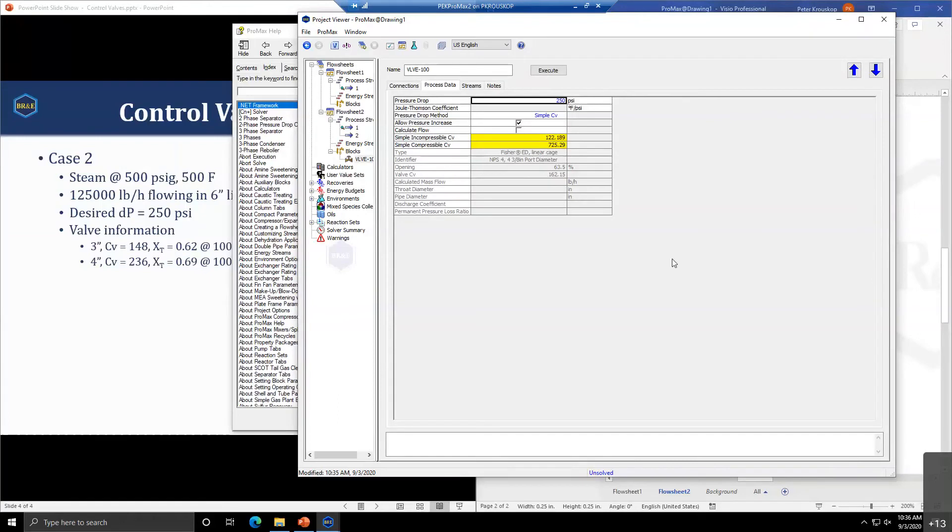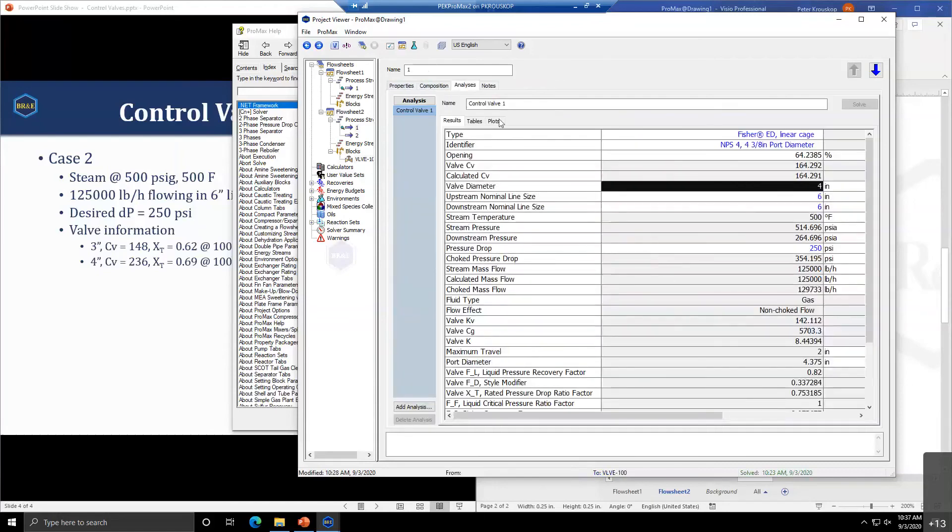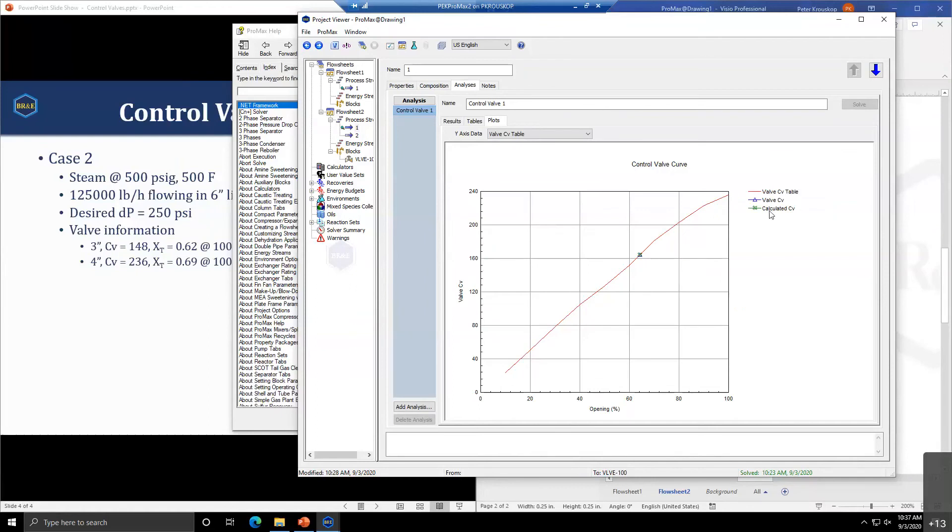The question is, does the analysis tool plot the open percent versus CV? Currently it does. Here in the plots, here is your valve CV as the percent open. You can see where your calculated CV is and where the valve CV is. In the tables, you can also get that tabulated percent open as a function of CV.